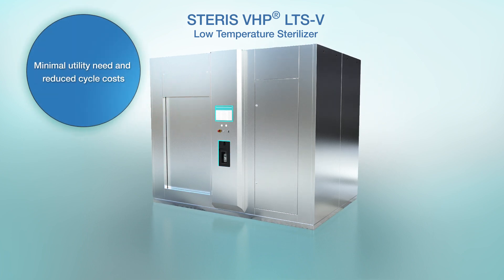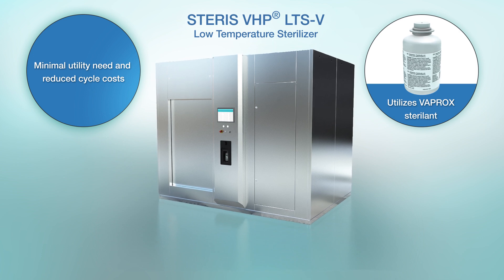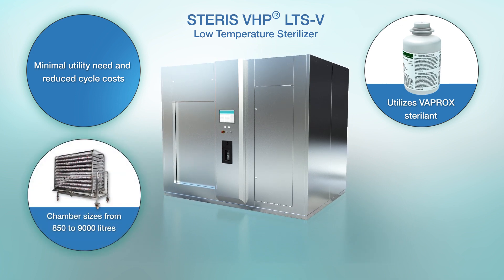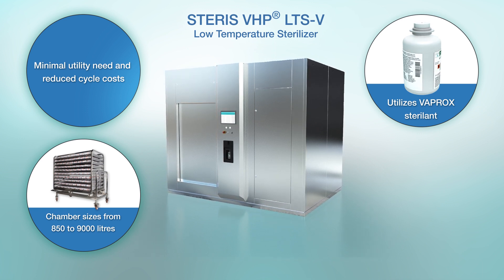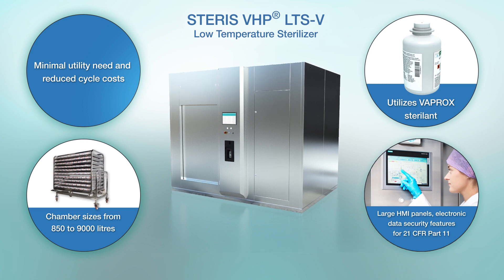The unit requires only readily available utilities such as water, 3-phase electricity and instrument air supply. The unit utilizes Vaprox sterilant that provides a validated, globally available peroxide supply. The LTS-V is available in a range of large chamber sizes to meet your production needs. The unit's design provides easy chamber and sterilant access, excellent usability via a large HMI panel, and electronic data security features for 21 CFR Part 11 and EU Annex 11 compliance.